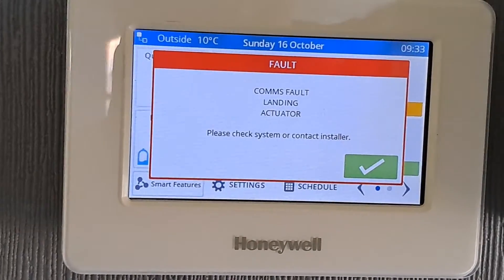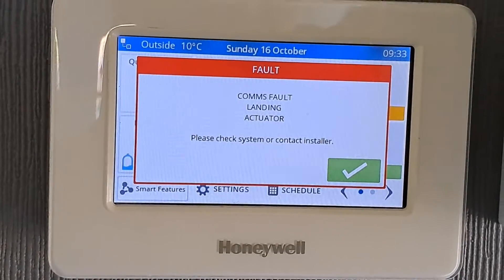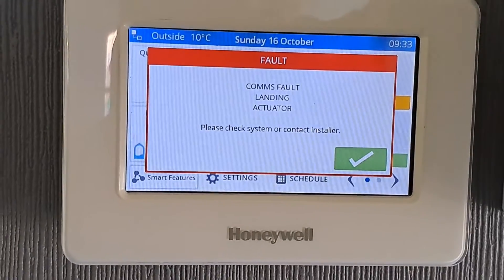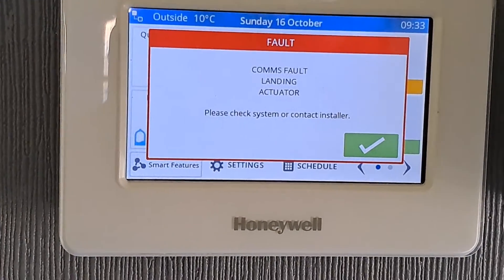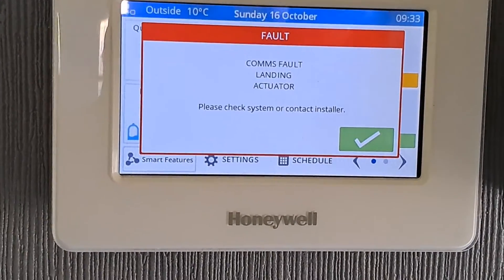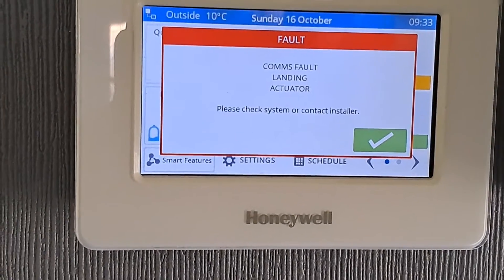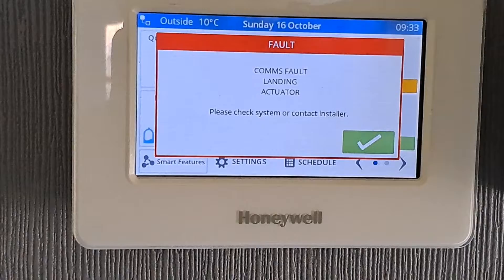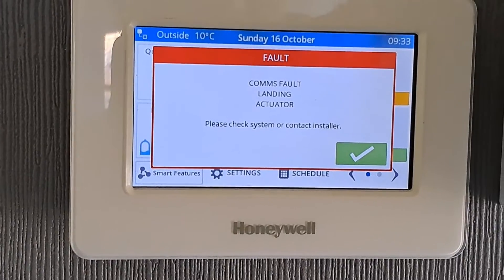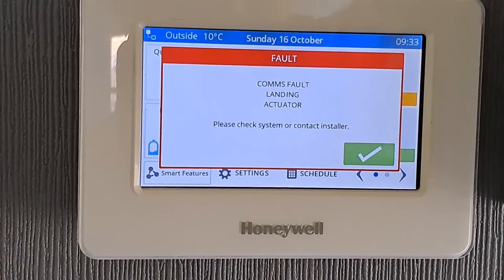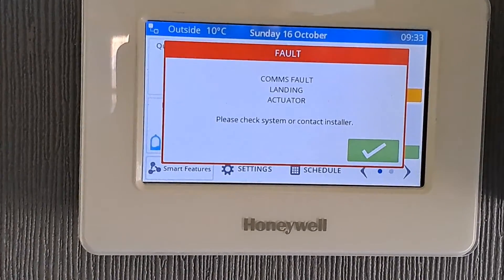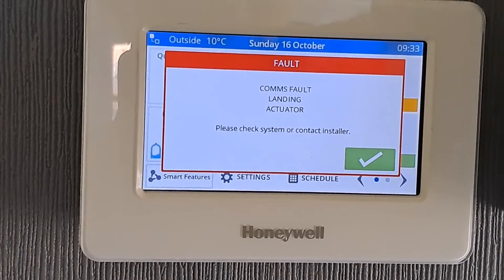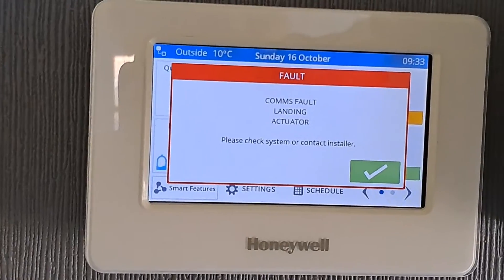All it means is the system is unable to communicate with that particular thermostatic radiator valve, or TRV. What's probably happened is the batteries have gone flat and just need replacing, so there's nothing to worry about.